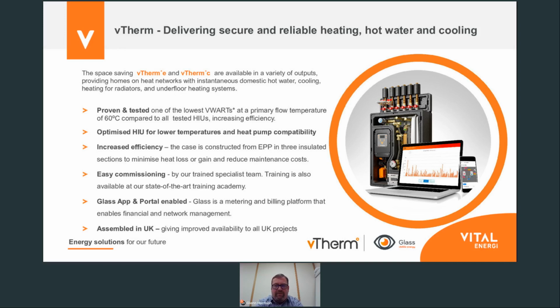So when a HIU gets installed into a customer's property, the system is commissioned by Vital engineers using an app-based digital platform. Essentially, that ensures that through the entire commissioning phase of the HIU, the parameters set up at the point of design are input into that system. So it gives us verification that the HIU is set up according to the design, and we're going to get the optimum benefit from it.